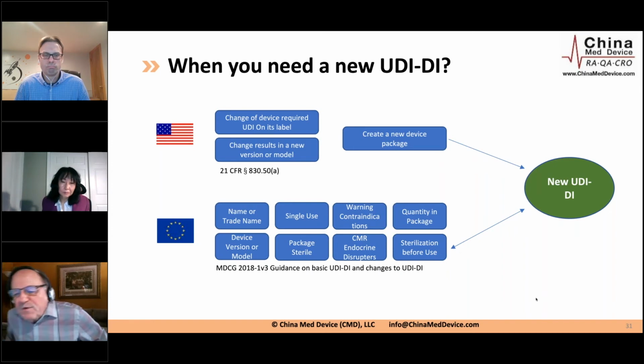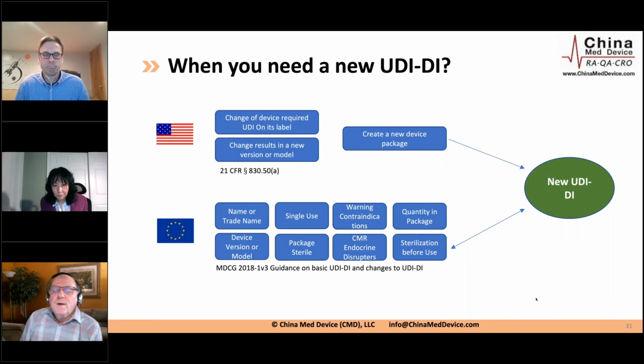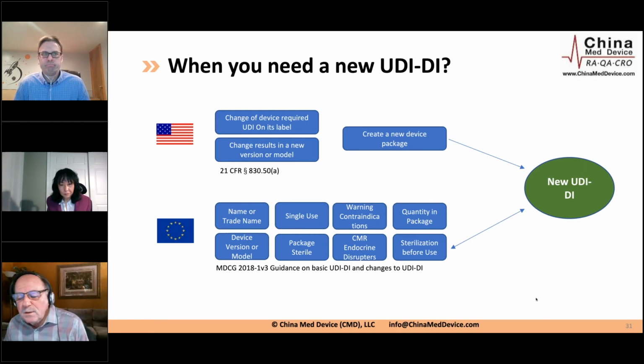Once you have a device identifier in place and registered, everything's good, you've reported everything, you might have changes to your product. Various things can happen. You might come out with a new model or version, and there might be changes to the label. There are time periods the FDA has for when you have to report those changes. If it's an attribute change where you keep the very same device identifier, and it doesn't cause a new version or model, but it's an attribute on the label, then you have to report that change before you commercially distribute that version of the new label. If it's not on the label, let's say it's an MRI field or some field that's not actually on your label, then you have about 10 days after you make the change to report it.